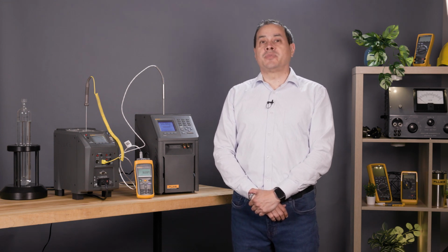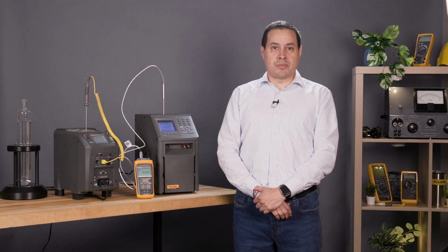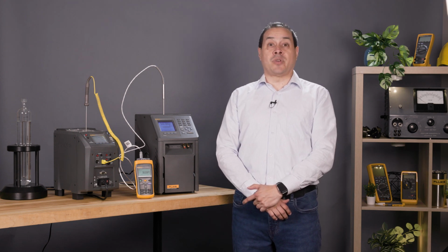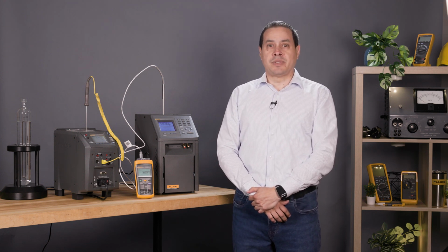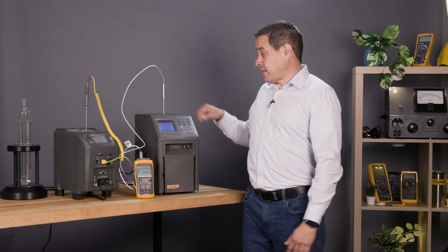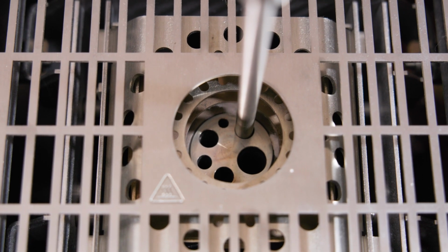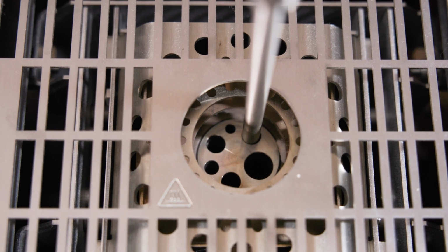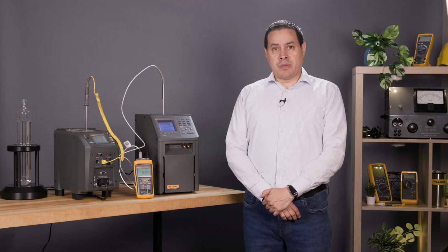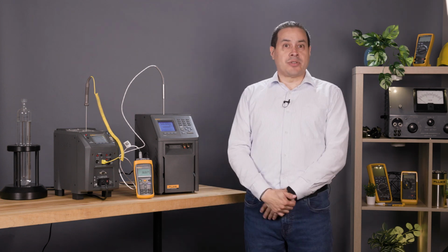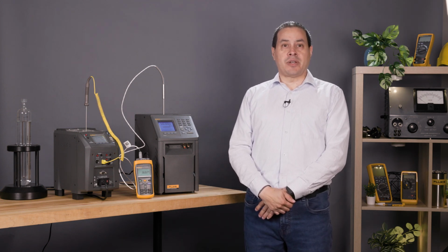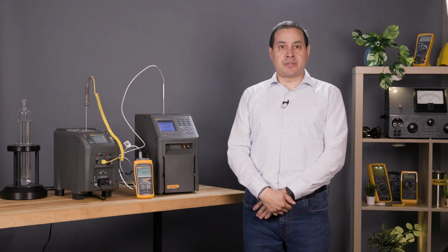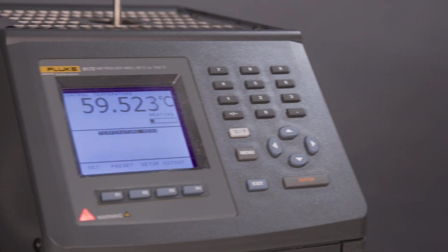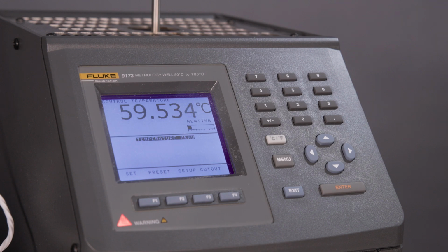And there's always pros and cons between a bath and a dry well. We want to have this experiment as a dry well because we want to reach high temperature. And there's always pros and cons, like the geometry of the hole. But always keep in mind your application. To use a dry well, always refer to the manual. Don't put any liquids in the inserts, and always check on the manual what the specs are, what the cutoff ranges are. The dry well should be selected by the range that is always dictated by your application.